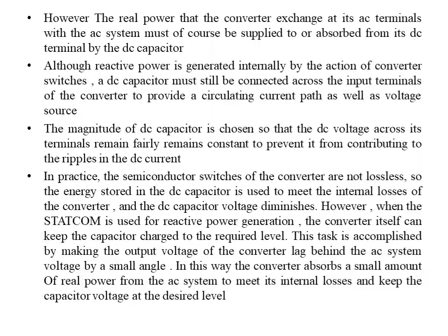Now this absorption of real power is mainly done by changing the phase angle between the voltage of the STATCOM and the utility bus. If we have control over the phase angle, we can have control over real power and reactive power. So by just controlling the phase angle, what does this STATCOM do? It absorbs the real power from the system and injects the reactive power into the system. And by absorbing the real power, it maintains the desired voltage of the DC capacitor, and at the same time it minimizes the losses of the semiconductor devices.